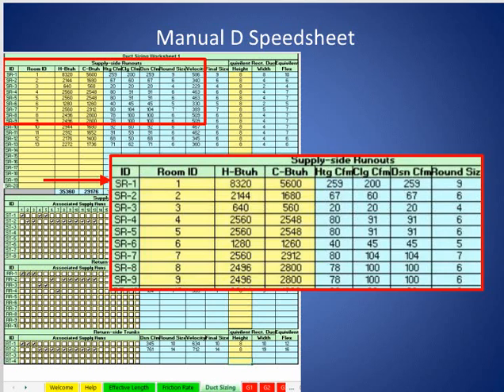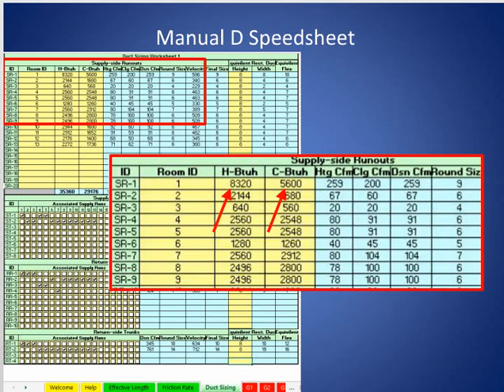Let's take a closer look at row one. Most people think in terms of room, and it says room ID. Some rooms have more than one diffuser, so I basically just number the diffusers — it's a diffuser ID, and also a room ID if there's only one diffuser. Number one in this case is going to be the master bedroom. We're going to enter 8,320 for heating BTUs per hour and 5,600 for cooling BTUs per hour right here on the form.